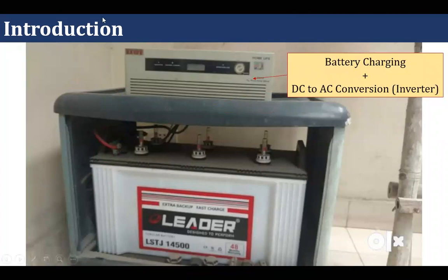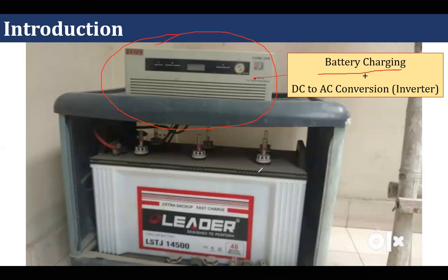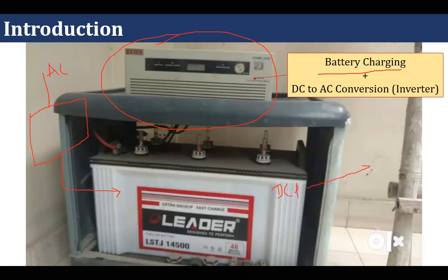Within this box, we have two types of circuits. One is known as the battery charging circuit. The whole system is connected with the AC mains. Whenever AC mains is available, the battery has to be charged. We know that from the input we have AC power, so we need a converter that will convert this AC power into DC power, and so this battery will be charged. If AC mains is not available, that time this battery has to give power to the load, and during that time this DC power has to be converted into AC. This will be done with the help of another circuit known as a DC to AC converter circuit, which is also known as an inverter.